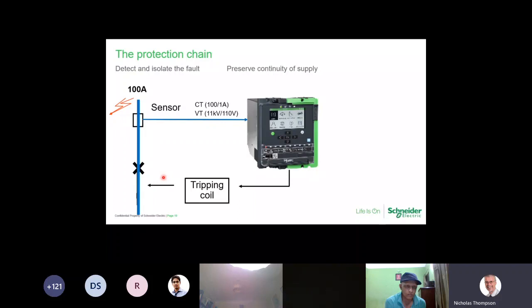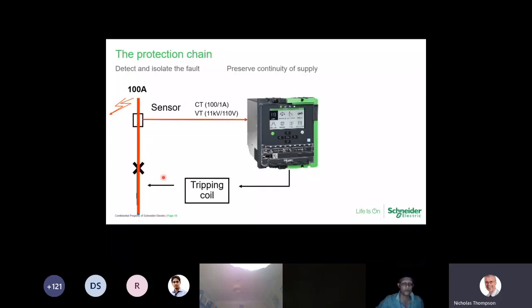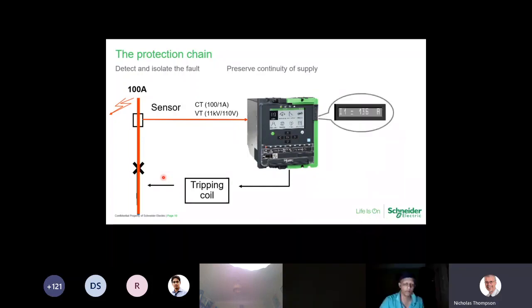So we've got our JCB, which has come along digging a trench, and everything's happy until they see a piece of cable at the end of the bucket. It's chopped through the cable. That's caused a fault on the cable. So what we're going to see is high current flowing to the point of the fault. The sensor will pick it up, translate that into a much lower current, and then our relay, which is constantly monitoring that, will pick up that we've got a very high current, and ultimately it's going to decide what it's going to do.